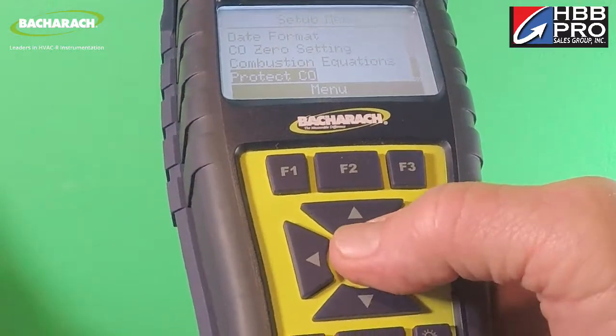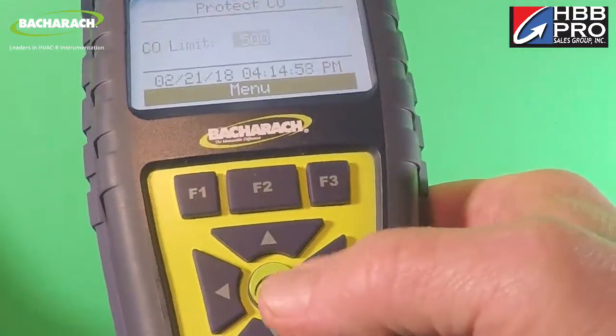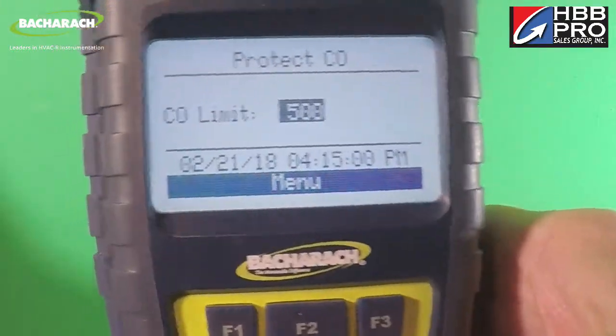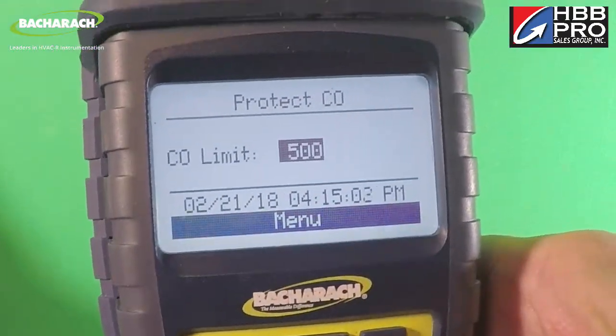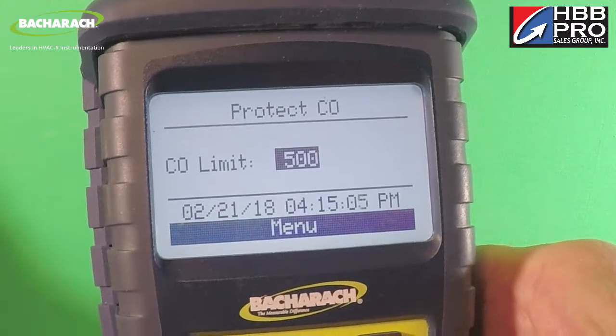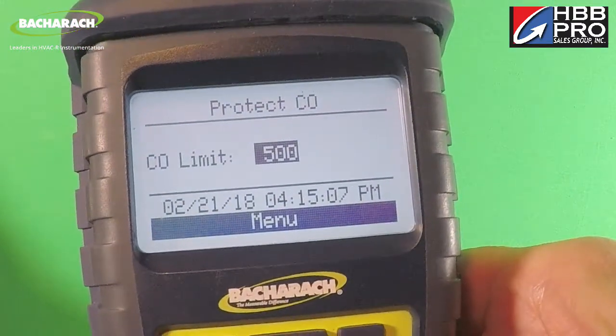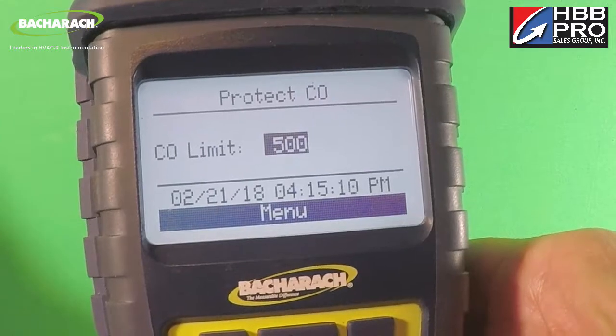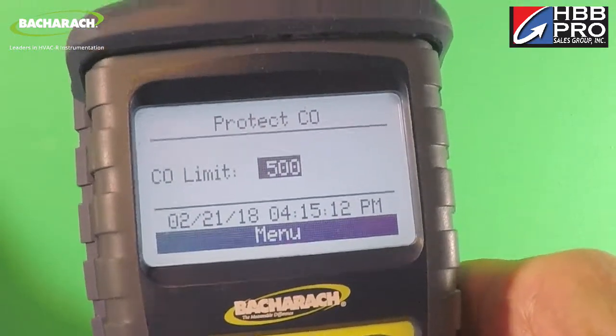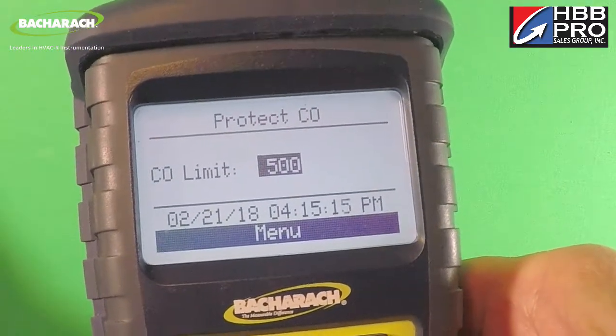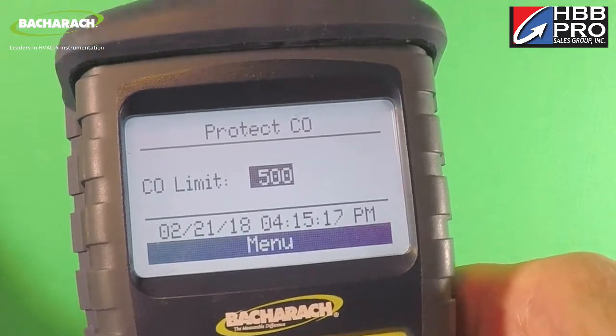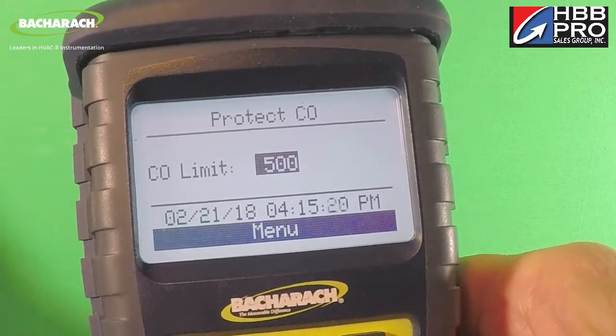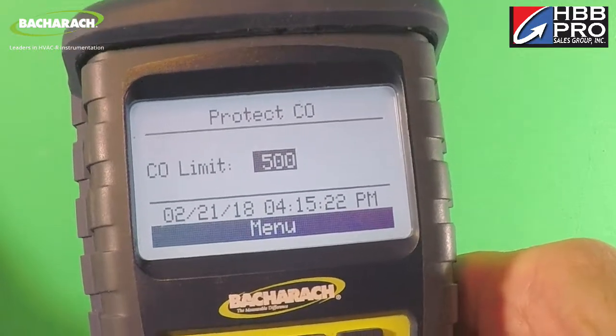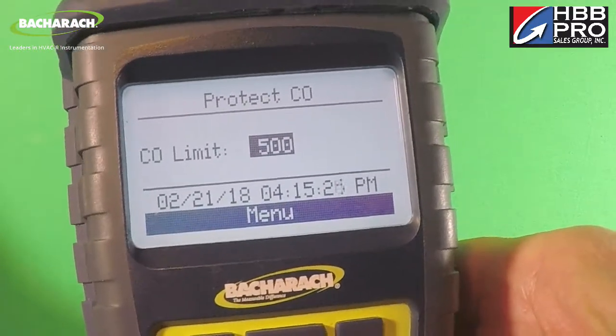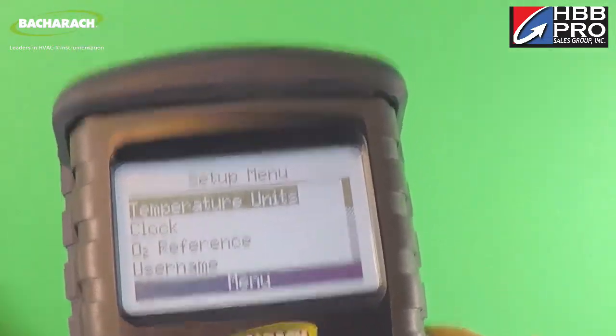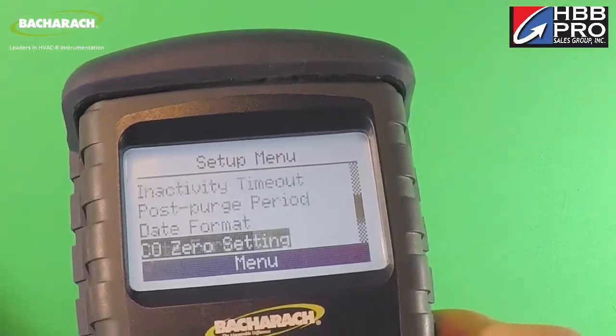Protect CO, that's not a bad thing to know about. We've got this one set for yes, and what this means is that if this instrument sees 500 ppm, it will shut the pump off to protect the sensor. These sensors are electrochemical in nature. The more of the gas that they're designed to detect, the more of that gas that they're exposed to, the shorter the life will be. So you want to try to keep the instrument from really getting slammed from carbon monoxide. I'd say set it for 500, maybe a little higher, whatever your preference is. Okay, so we'll back out of that.